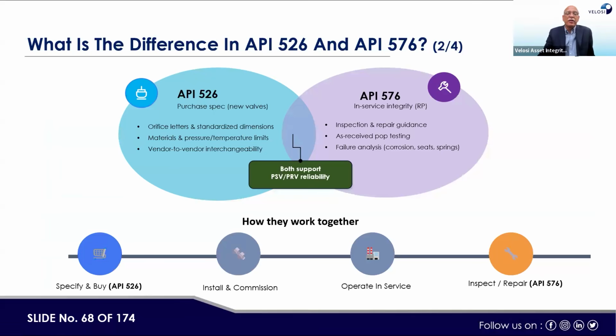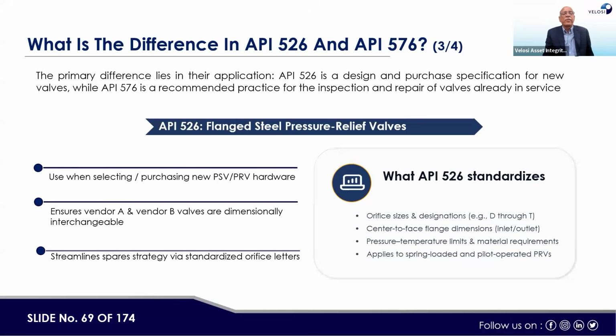Plant inspectors and maintenance personnel use this during the operational life of the valves. Then, if you see the life cycle, in the initial phase we specify and buy, install and commission. Up to this point it is separate, but specify and buy is API 526. Install and commission is API 520. Then operate in service, inspect and repair is API 576. So this is the flow of information, how these standards work together. If you start with 520, 521, then 526, then 576, this way the standards are correlated with each other.